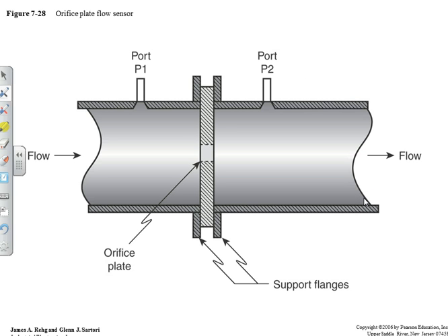Now we want to know how much flow we have. So I've got some flow coming in, and I put an orifice plate in there. Normally that's a little small, so I'm not going to have much flow through the orifice plate. Then I have some pressure difference on either side of the orifice plate, and that difference in pressure is what I use to determine my flow. So if I have 1 pound difference, then I have 30 gallons per minute.